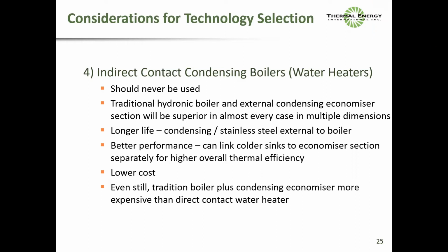Oh, I didn't see that you unmuted, but I was just going to ask, what about oil boilers? My understanding is that condensing ones are not the greatest idea, but if you do it separately, like you're suggesting, does that mean there is now an application to add this condensing section to a traditional, mid-efficiency oil boiler? Absolutely. But in that case, I would not recommend an indirect, because the indirect will still suffer from sulfuric acid dew point, and will corrode. But you can take a traditional oil boiler and put a direct contact unit and achieve condensing efficiencies.